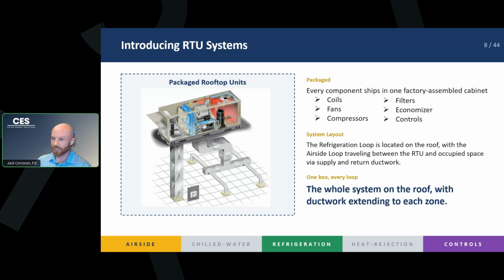So essentially, this is where our two loops, the refrigeration loop and our air side loop, intertwine, right? And we'll have the refrigeration loop entirely located on the roof in the cabinet, but the air side loop actually extends into the building, and the ductwork is what allows that air to travel from the occupied space into the rooftop unit on the roof. So essentially, the whole system's on the roof, and you got ductwork extending down into each zone.